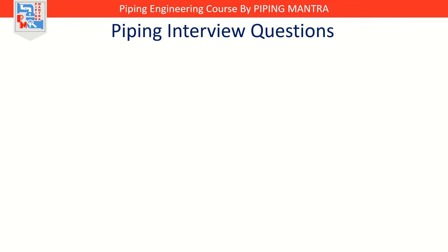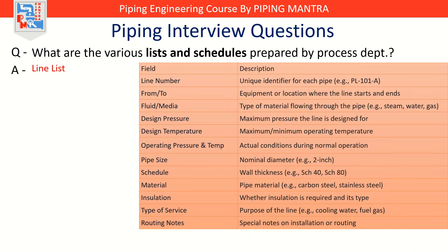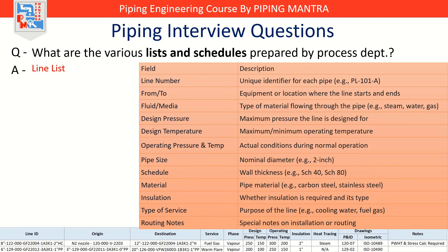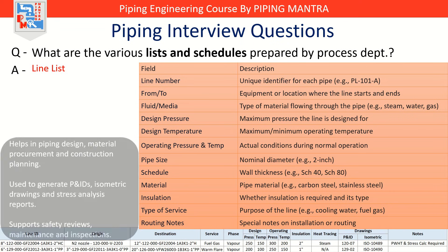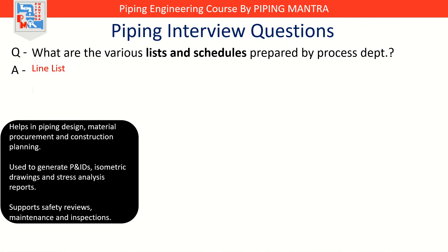Now that we know the main diagrams, the next question is: what are the various lists and schedules prepared by the process department? Lists might not sound exciting, but they are the backbone of process engineering coordination. First is the Line List — this is like a master register for every single pipeline in the plant. It includes line numbers, sizes, specifications, operating conditions, design conditions, test pressures, painting requirements, and coating details. It helps with piping design, procurement, and construction planning, and supports safety reviews, maintenance, and inspections.